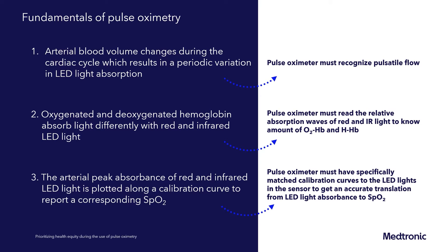Oxygenated and deoxygenated hemoglobin absorb light differently with red and infrared LED light. Pulse oximeters must read the relative absorption waves of both red and infrared light to know the amount of oxyhemoglobin and deoxyhemoglobin. Finally, the arterial peak absorbance of red and infrared light is plotted along a calibration curve to report a corresponding SpO2. Pulse oximeters must have specifically matched calibration curves to the LED lights in the sensor to get an accurate translation from LED light absorbance to SpO2.